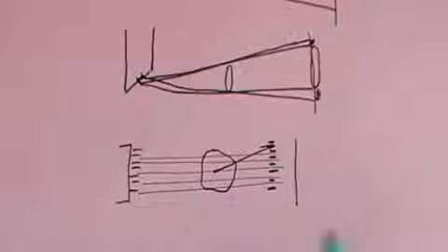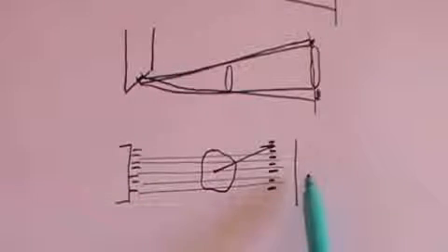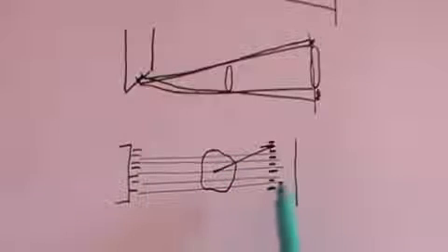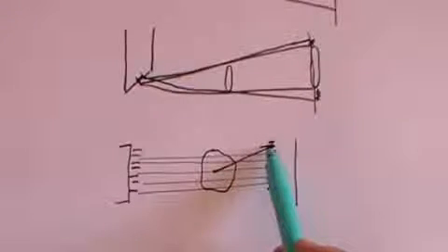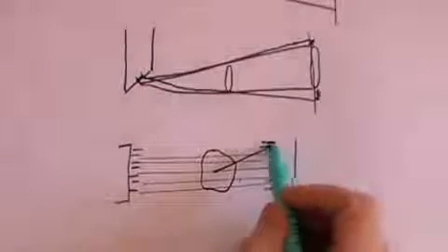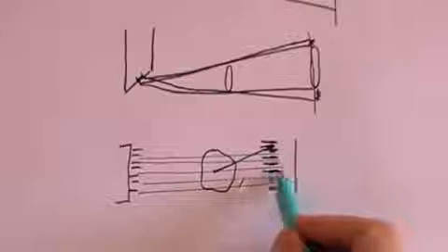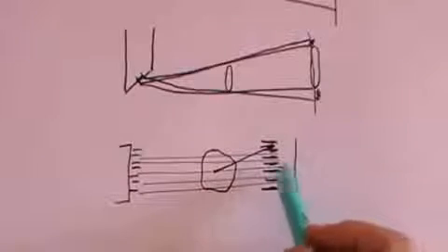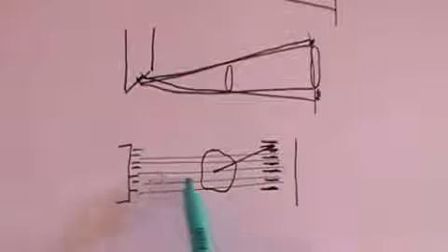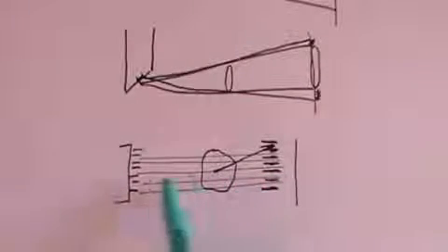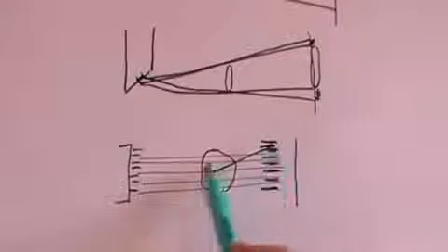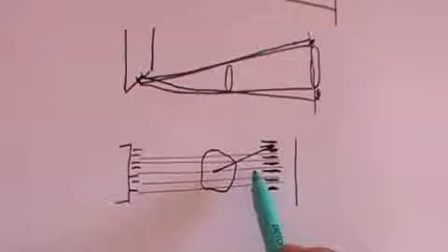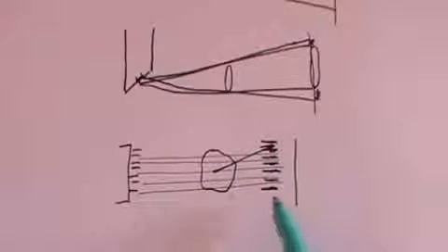by the grating. And so only X-rays which pass straight through the piece of tissue in the body and then through the grating will hit the photographic plate. All X-rays that have been deflected will just simply hit this piece of lead and be absorbed. The lead grid, of course, typically will have to be quite wide to ensure that only X-rays which are travelling parallel from the X-ray tube pass through and hit the screen. Any X-ray which is travelling at an angle as a result of having been deflected will be absorbed by the lead grid.